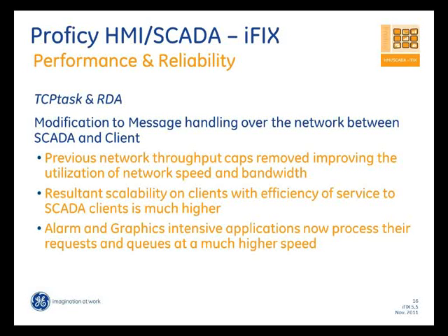We have tested it to go almost to about 2,200, 2,500 transactions. What that has improved is really the network throughput of the SCADA. So the speed at which the SCADA now processes the alarms and the data queue to the client has really improved, and we've seen a tremendous benefit in terms of how the whole network is serviced. So that's one big improvement that we have seen as part of this initiative.